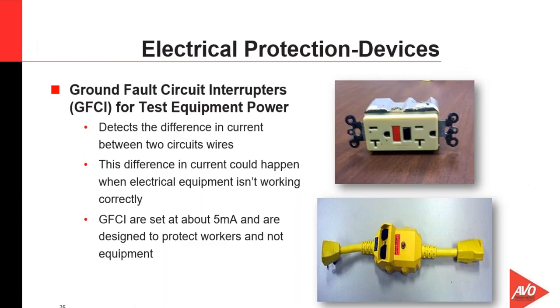Some of these issues here, the ground fault issues, this is ancillary to testing, but we also need to make sure that we protect our test voltage going to our test equipment. We have protective circuits and methods of using GFCIs and things for that type of testing. So we want to make sure that we're protected even from our supply source.